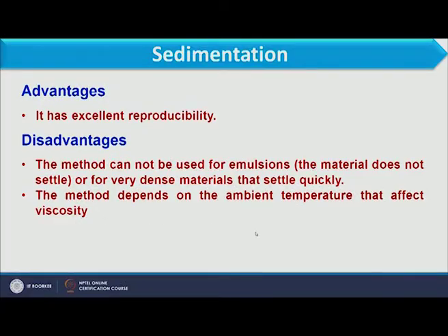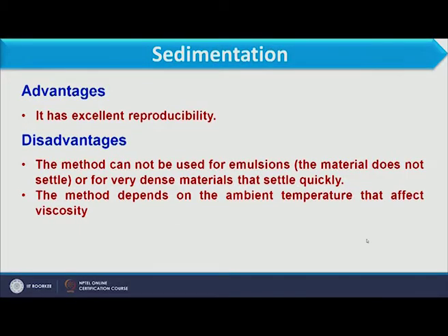The second disadvantage is that the method depends on the ambient temperature, which affects viscosity. That is a disadvantage because usually the sedimenters are open tank equipment, open to the environment. So, when the temperature reduces in winter, the viscosity of the solution will increase and it will not allow the particles to settle faster.